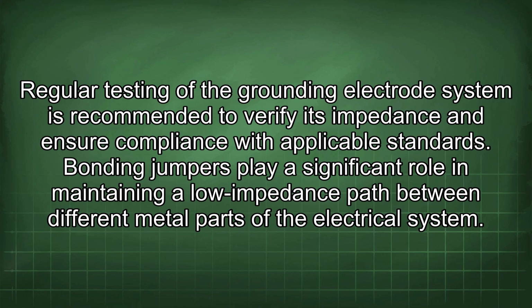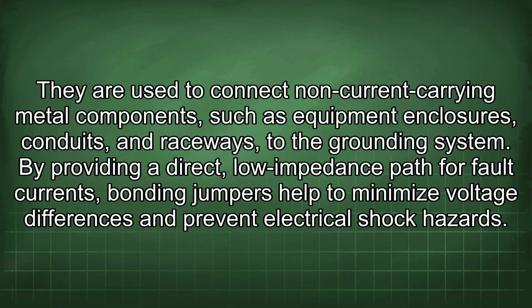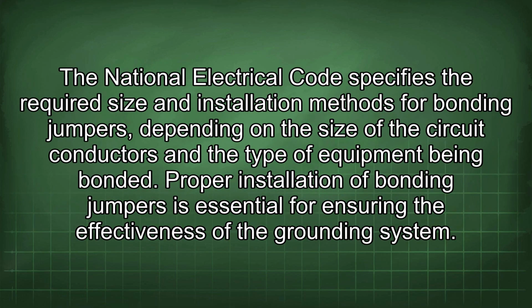standards. Bonding jumpers play a significant role in maintaining a lower impedance path between different metal parts of the electrical system. They are used to connect non-current carrying metal components such as equipment enclosures, conduits, and raceways to the grounding system. By providing a direct, low impedance path for fault currents, bonding jumpers help to minimize voltage differences and prevent electrical shock hazards. The National Electrical Code specifies the required size and installation methods for bonding jumpers, depending on the size of the circuit conductors and the type of equipment being bonded. Proper installation of bonding jumpers is essential for ensuring the effectiveness of the grounding system.